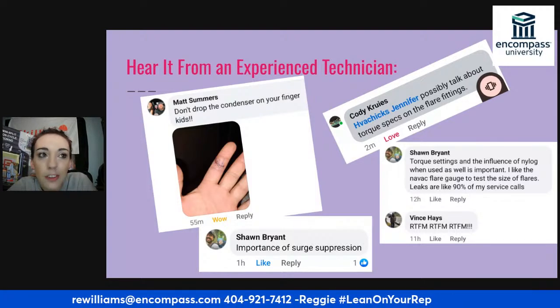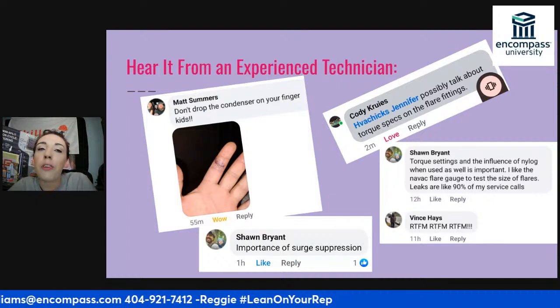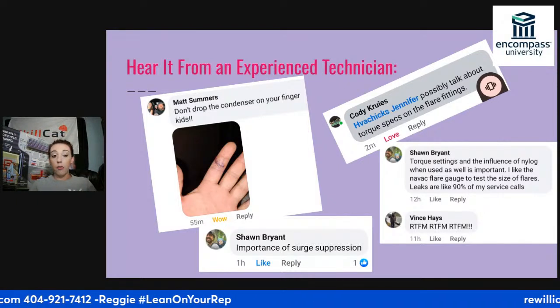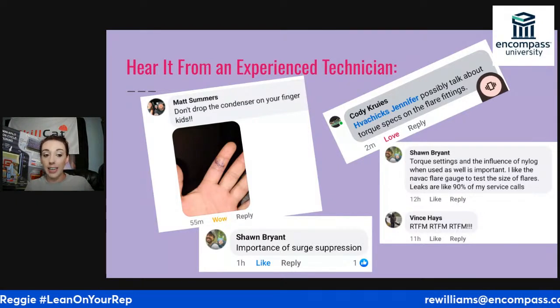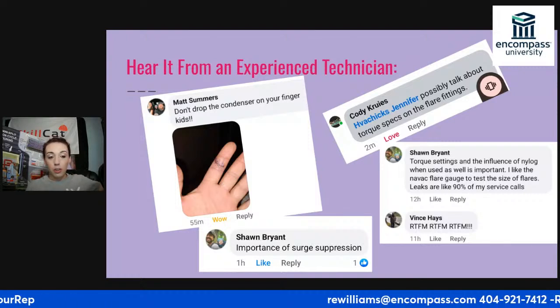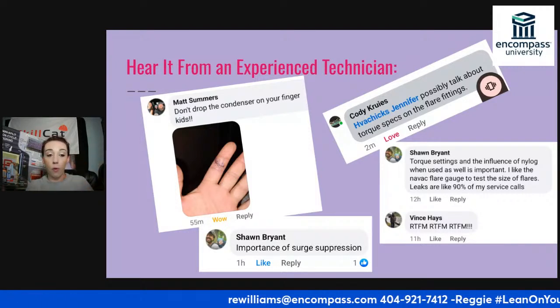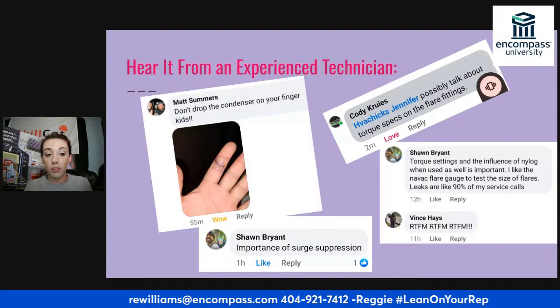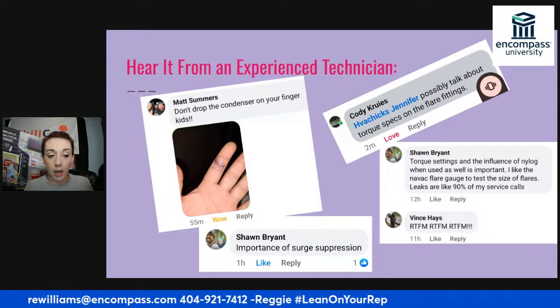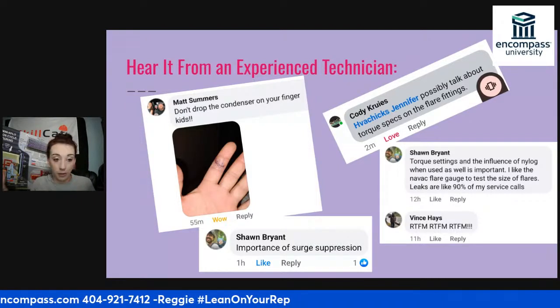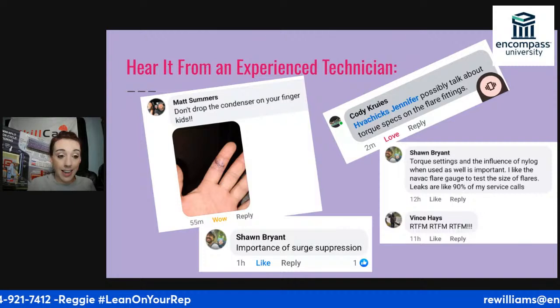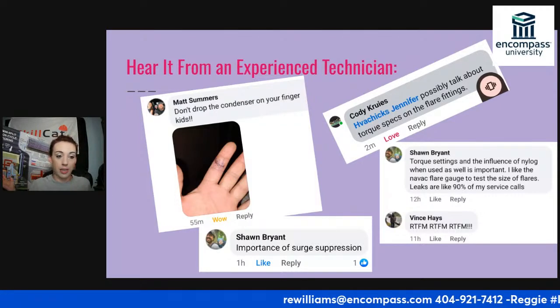Or surge. When surge happens, the voltage comes from the disconnect and directly backfeeds. So you have your 24 volt side, but when a surge happens, it throws high voltage throughout your entire unit. So when your contactor, capacitor, and compressor see that high voltage, they're cooked immediately.